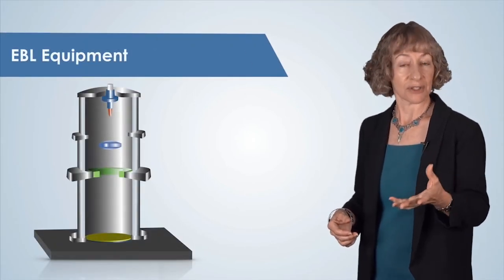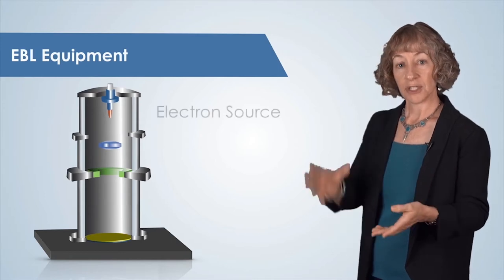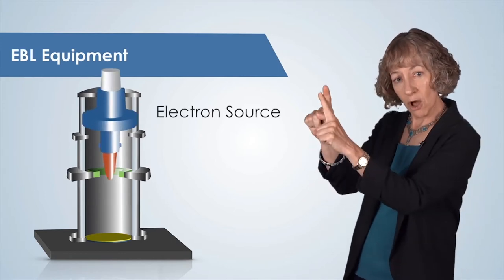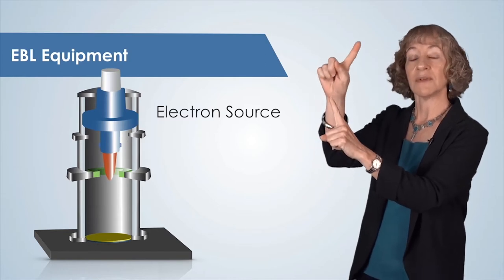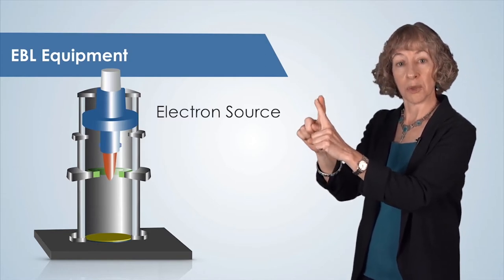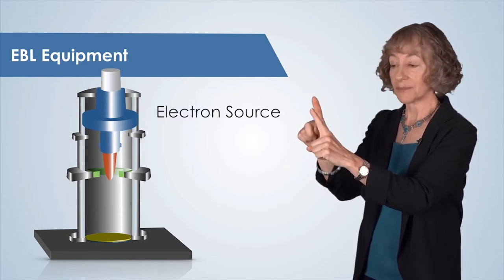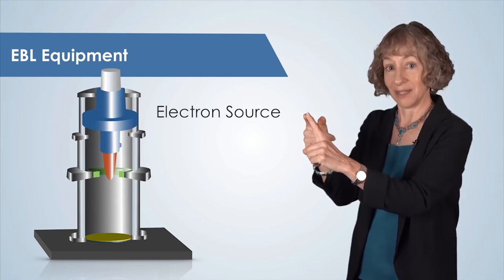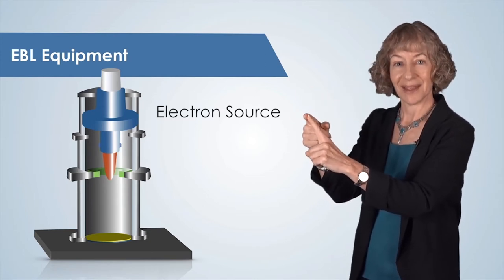The EBL is quite a complex instrument, but its basic components are as follows. There is an electron source, which is a small, sharpened tip that emits a stream of electrons when a high-voltage bias is applied. We call these emitted electrons the electron beam.